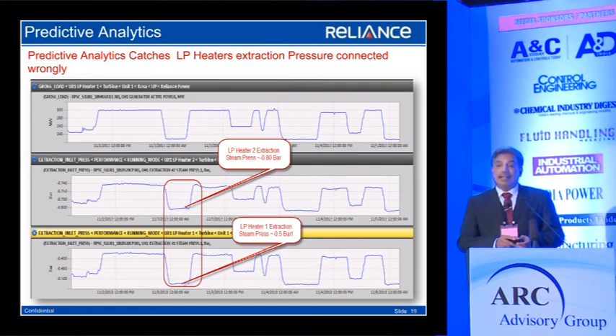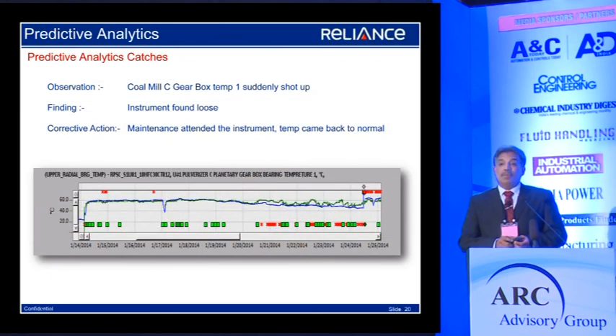Second was another instance where the coal mill temperature suddenly shot up. The root cause was that the instrument was found loose due to vibrations. This could have led to a unit tripping. If the coal mill had tripped, the unit would have tripped, causing a loss of at least 10 million rupees. So every tripping avoided is a direct saving of 10 million rupees to us.